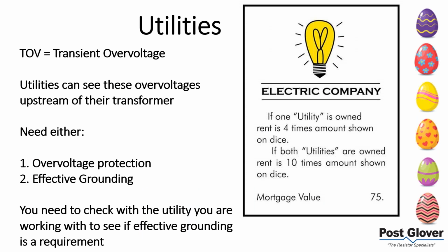One thing I do want to mention is for utilities. This is not really an afterthought, but it's not a big part of the technical issues, but it's a big part of the application issue, because a lot of times utilities have transient over voltage, that's a TOV. They have to worry about potential over voltages when they are working with most likely a wind or solar application. And they need some kind of overvoltage protection. Typically this happens in an islanded situation where you have a ground fault. You might have some over voltage problems there, and that could be seen by the utility upstream.